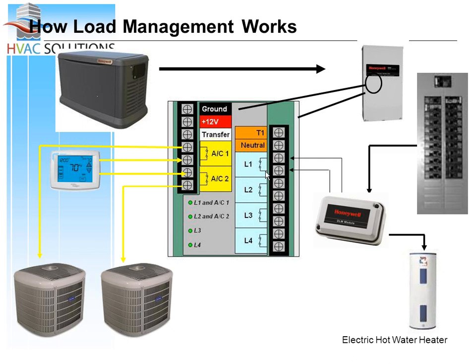Say, well, we're pretty close, so I'm going to shed it, but I want it to have high priority. So now what we do, we take that well pump, we put it in L1. But we take the air conditioner, and instead of putting it at AC1, we're going to put it down to AC2. So that the first thing that comes on is the well pump. Second thing would then be the air conditioner. Then we can look at, you know, dryers and ranges and other things like that.